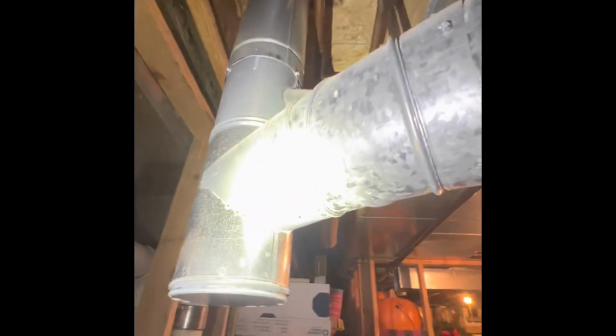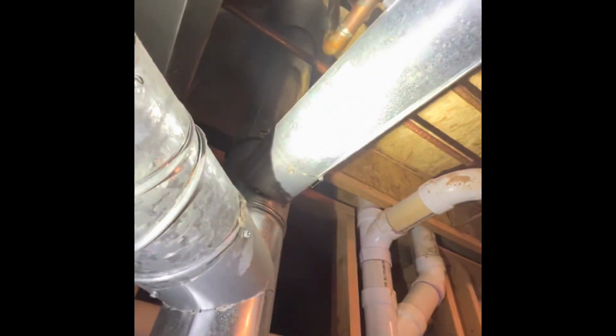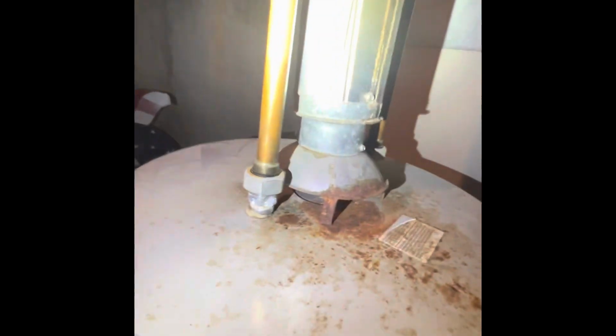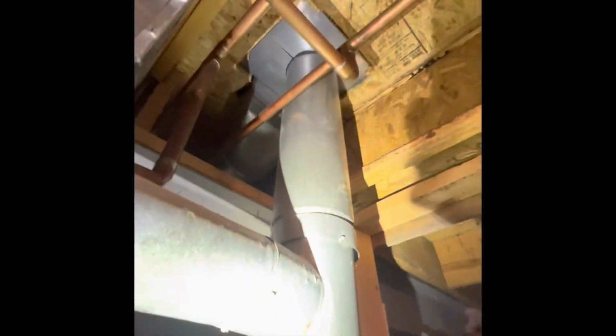It's a standard efficiency. We're going to a stack, coming off with a 4, going to a, I think it was a 5x5x4. We'll run a new 3-inch back to the hot water tank as well if we're not replacing it, and then a 4 back to our new furnace. Goes through a stack, 5-inch, send a new T as well.